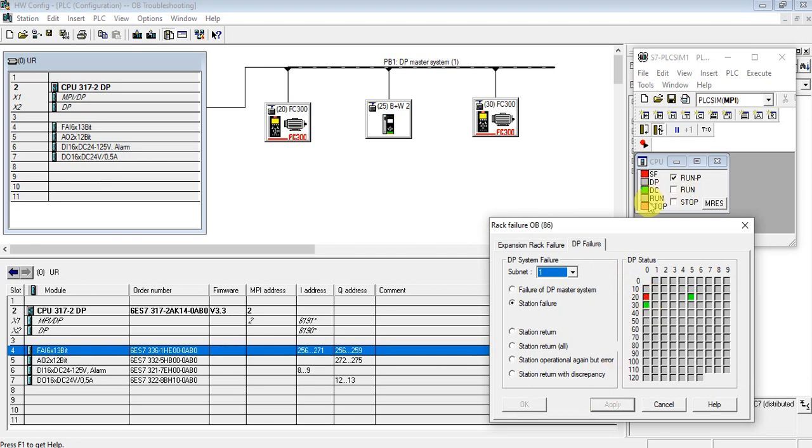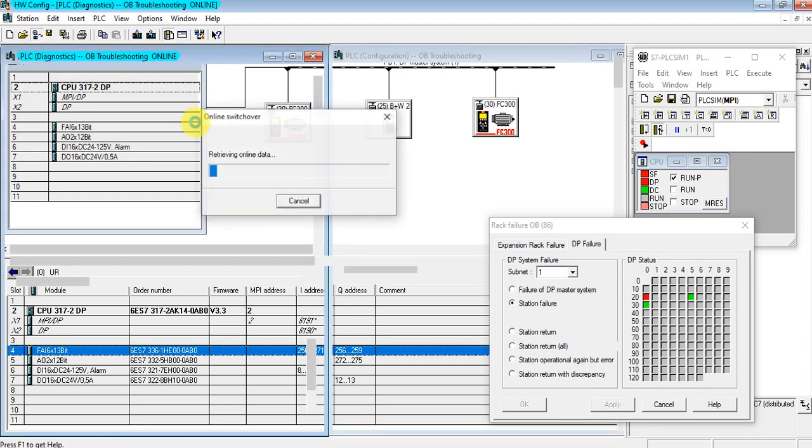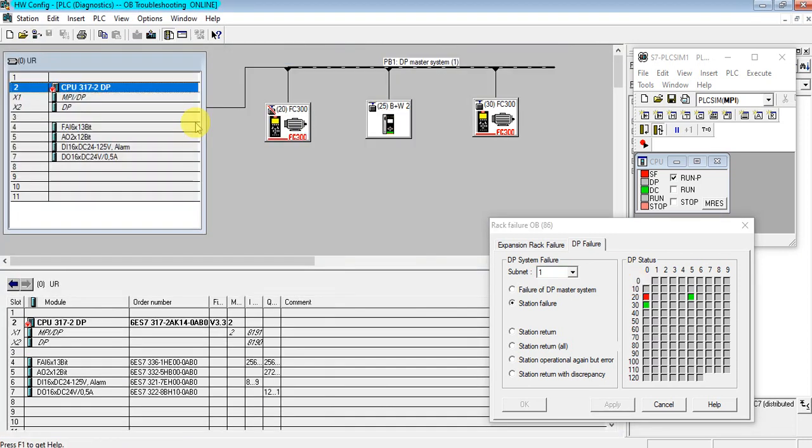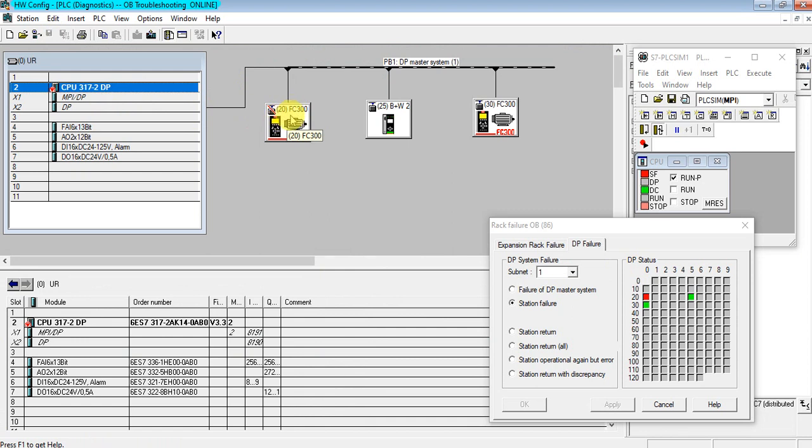As you see the CPU goes to STOP mode and shows some DP fault or Profibus fault. So without OB86, the CPU goes to stop mode. Let's see the diagnosis buffer first. As you see, the slave is missed.